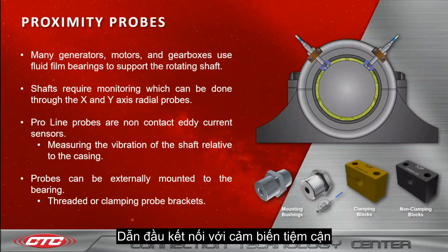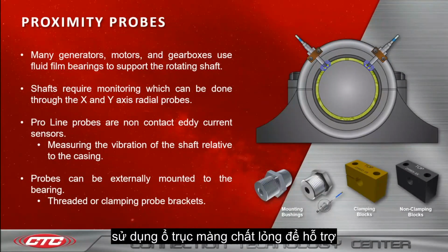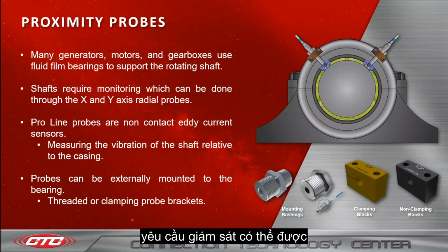That leads us into proximity probes. Many generators, motors, and gearboxes use a fluid film bearing to support the rotating shaft. Shafts require monitoring, which can be done through the X and Y axis radial probes. You can see on the picture to the right that the proximity probes are mounted on the bearing 90 degrees apart for the X and Y axis reading. Our ProLine probes are non-contact eddy current sensors, which measure the vibration of the shaft relative to the casing.